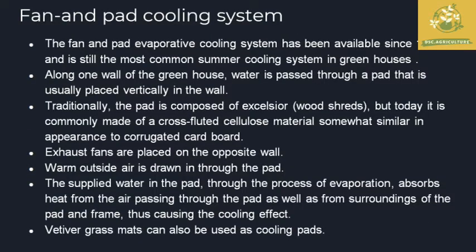The fan and pad evaporative cooling system has been available since 1954 and is one of the most common cooling systems in greenhouses. In the design, along one wall of the greenhouse, water is passed through a pad which are usually placed vertically in the walls, so when air circulates from the fan the heat is reduced. Traditionally the pad was composed of excelsior — wood shavings — but today it is commonly made of cross-fluted cellulose material, similar in appearance to corrugated cardboard.